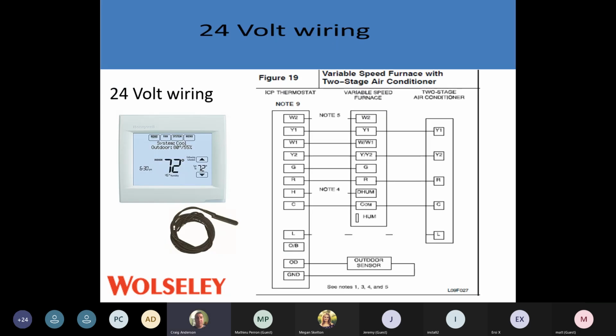24-volt wiring. You're going to get into 2-stage air conditioners. You're going to be working on heat pumps as well. Not really a heat pump, we're getting into cooling season, but be mindful of what you're testing outside. 2-stage air conditioners: Y1, Y2 is your 24 volts for your staging outside. R and C, depending on the unit outside, you might not have an R, but you'll have C out there for your common.